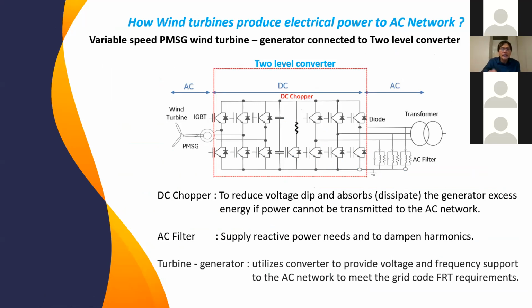How does the turbine produce the energy? A variable speed wind turbine generator is connected to a two-level converter. So when the turbine produces the energy, it should be connected through a converter. Currently, there are 2 types of converter used in turbines. What we saw here is a 2-level converter, but the turbine can also be connected to a 3-level converter. We discussed the converter in our presentation in November. From this converter, it is connected directly to the AC network. We still need a DC chopper here, and a filter here, whose function is to supply reactive power needs and to dampen the harmonics produced by the turbine.